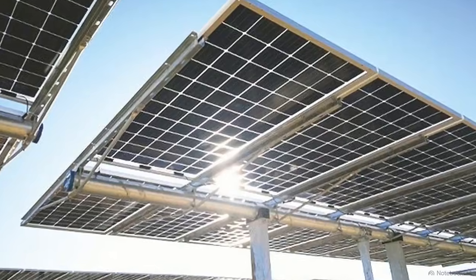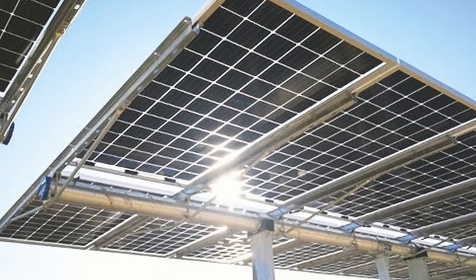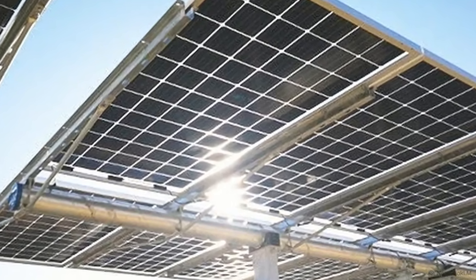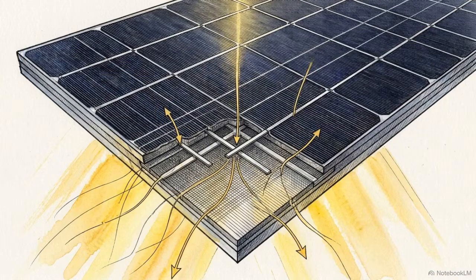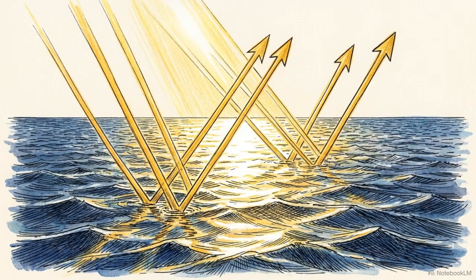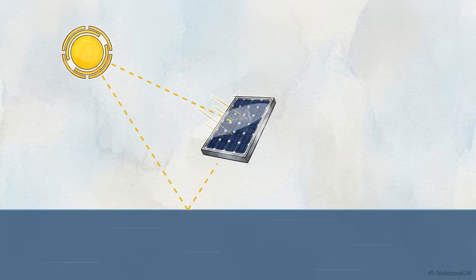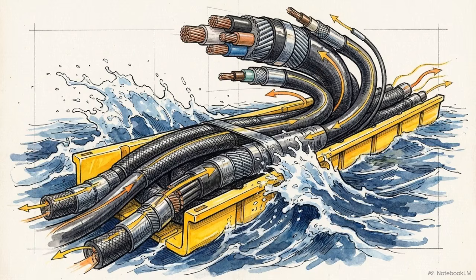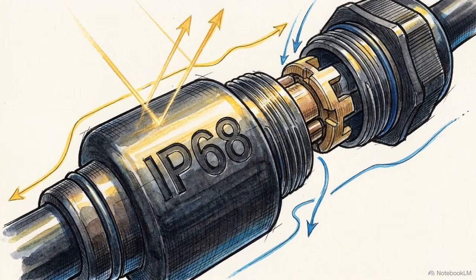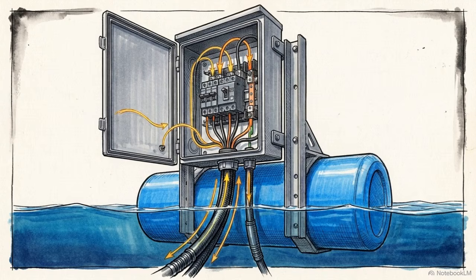Up on the platform, developers are moving away from standard solar panels. Instead, they increasingly specify bifacial monocrystalline modules, which are coated in photovoltaic material and active on the rear side as well as the front. Because water naturally reflects sunlight, these bifacial panels can capture the surface albedo, bouncing that light into the rear of the module and generating an additional 3 to 6% energy boost. The direct current electricity generated by these panels must immediately be protected from the wet environment. The power flows into heavy-duty IP68-rated waterproof flexible cables, engineered to withstand both harsh UV rays and continuous wave motion. These cable strings route the electricity into weather-resistant combiner boxes.